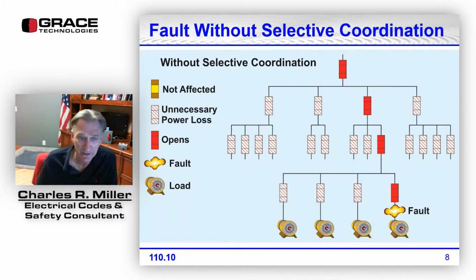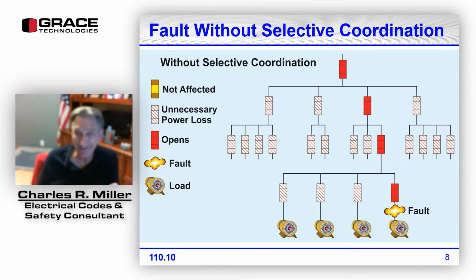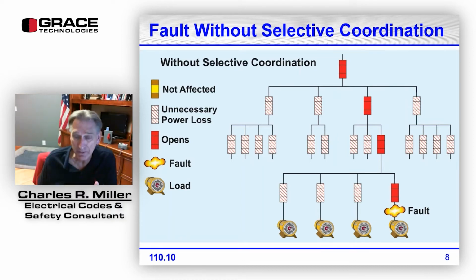So here's the illustration. We have a fault in a branch circuit. The branch circuit overcurrent device tripped, but other things tripped up the line as well. In fact, everything up the line tripped. What that means is the fuse with the red stripe means that all of these other things were disconnected from power. They lost power unnecessarily. All right.